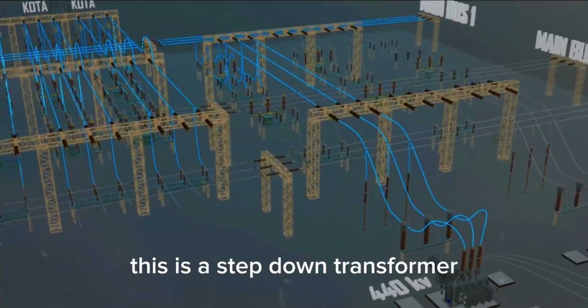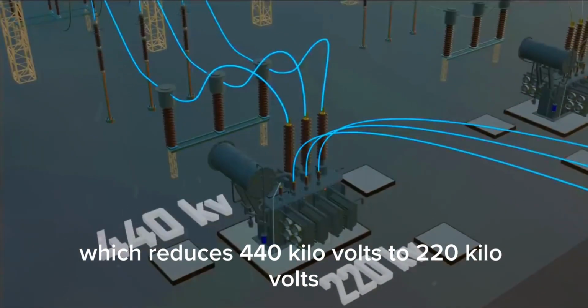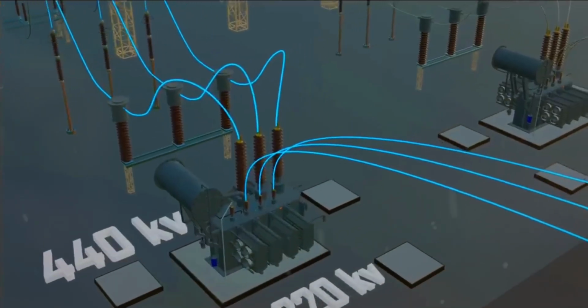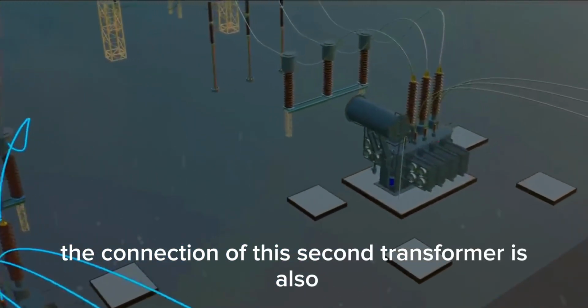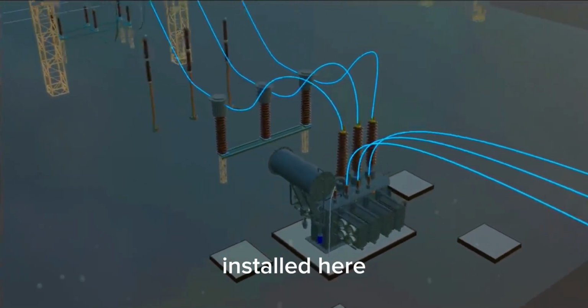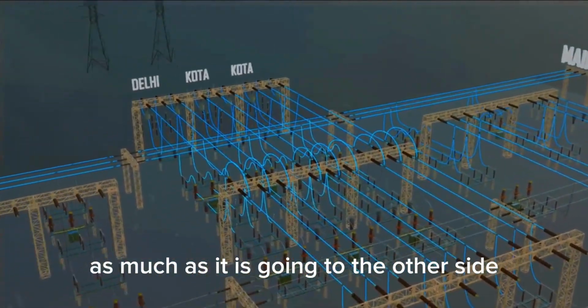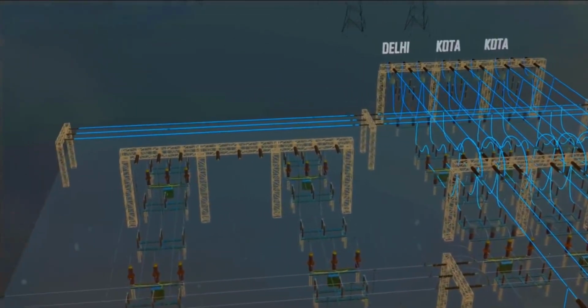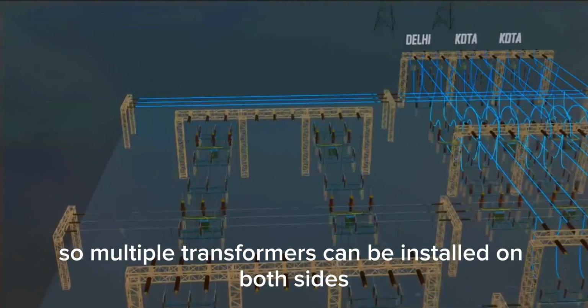This is a step-down transformer which reduces 440 kV to 220 kV. In the same way, the connection of this second transformer is also installed here. Now this main bus is coming here as much as it is going to the other side. So multiple transformers can be installed on both sides.